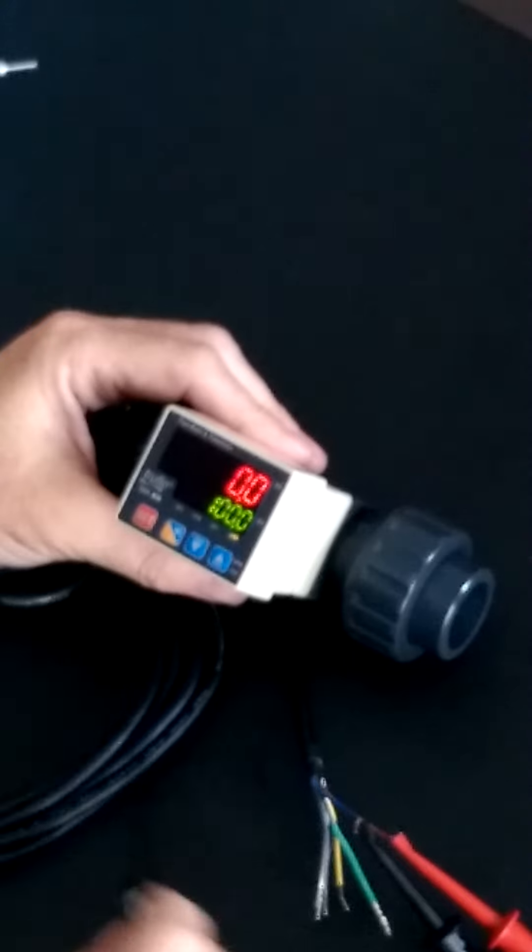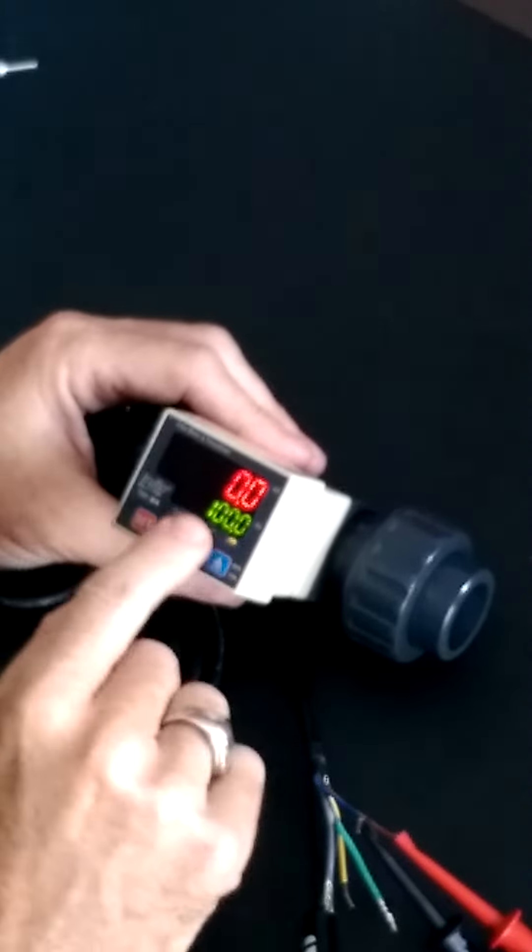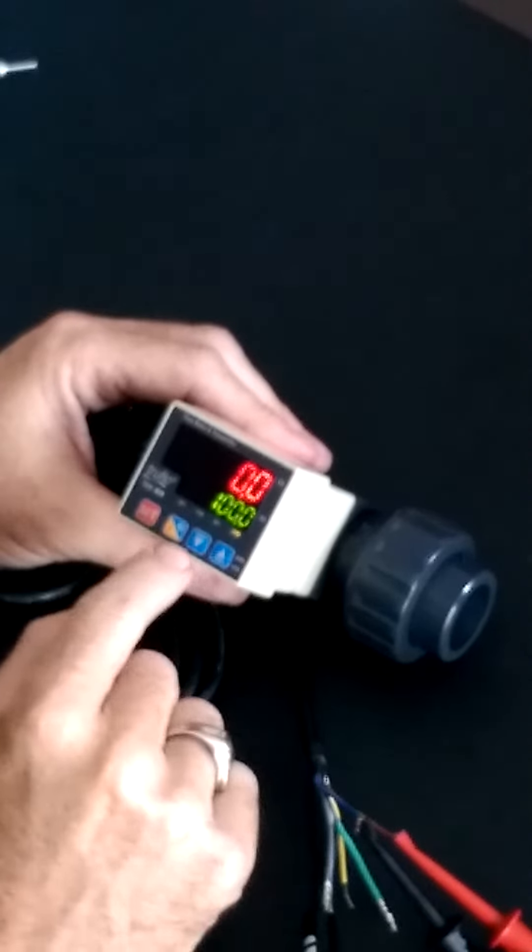Right now the selected value is 100. So we would need more than 100 gallons going through our system before that pulse output turned on. Otherwise it would stay off.